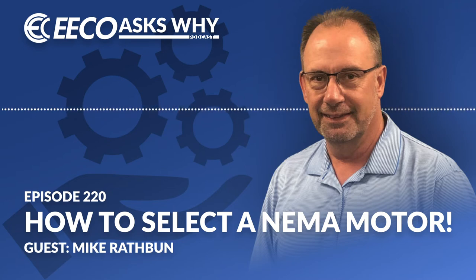I think this really impacted me at one point in my career when I was working in the automotive industry, specifically in large stamping press designs, where you have a motor that is spinning a very large flywheel. Think of a flywheel rotating on a large bearing that may be 50,000 pounds. The way that motor needs to respond to that load to speed it up and slow down obviously has to be much different than if that was a pump that was just pumping water. So some attention to the design. The design designation, whether that be A, B, C, or D, could have a significant impact on the reliability of that motor and its capability to perform with any given application.